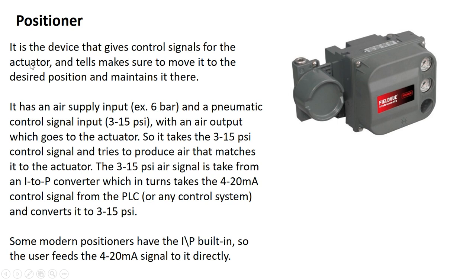The positioner is the device that gives control signals to the actuator. It ensures the actuator moves to the desired position and maintains it there. For example, if you want the valve 40% open, the positioner sends the actual air signals to the actuator so that it achieves and maintains that percentage. It has an air supply input — for example 6 bar — a pneumatic control signal of 3-15 PSI, which is an industry standard, and an air output that goes to the actuator.